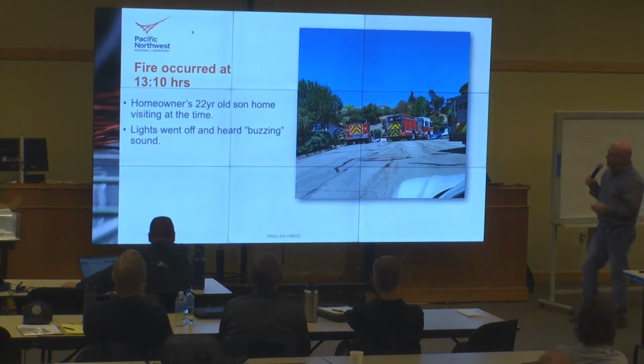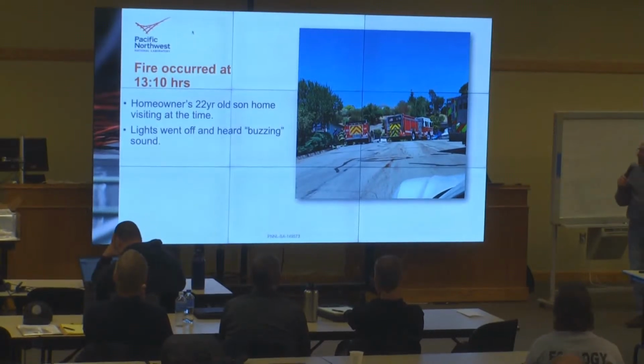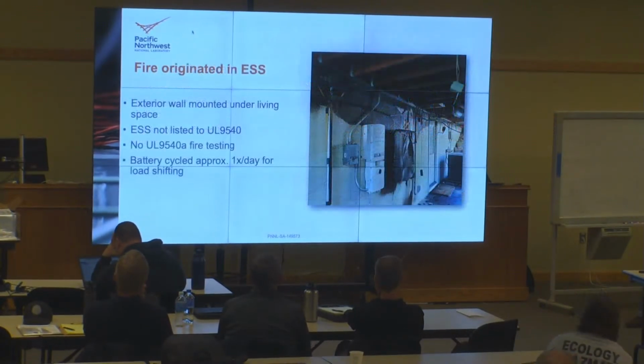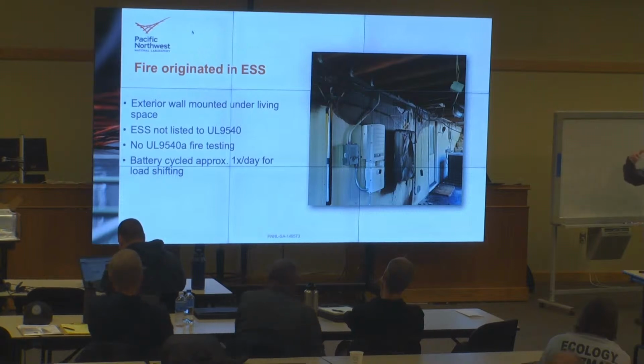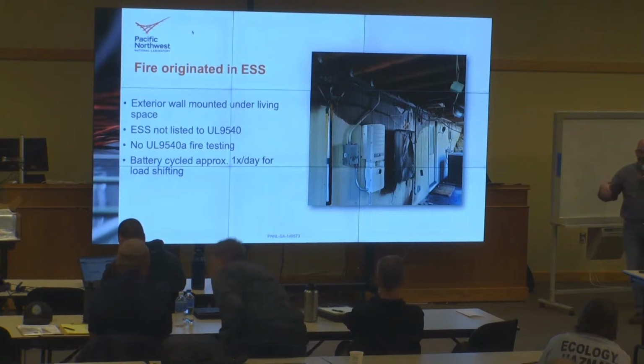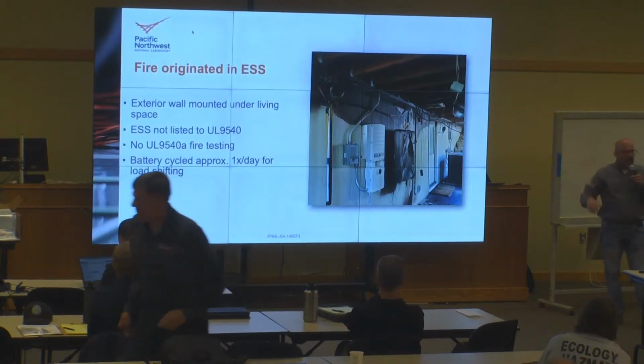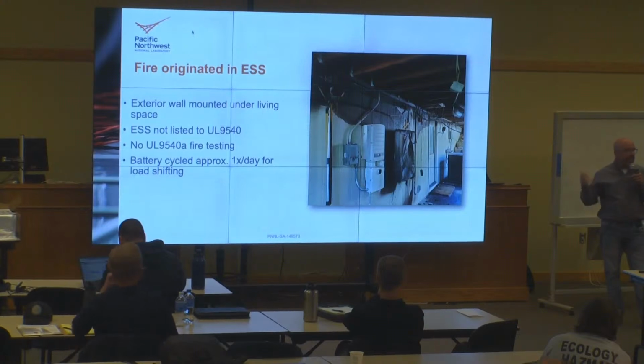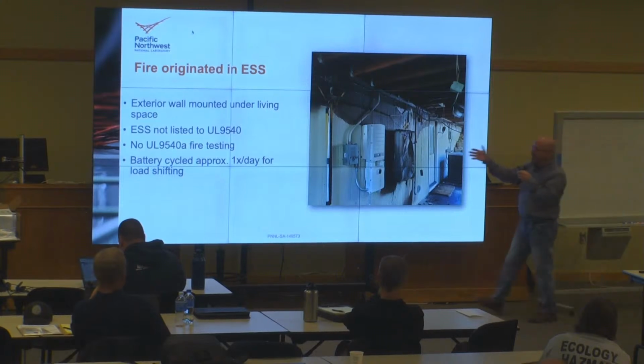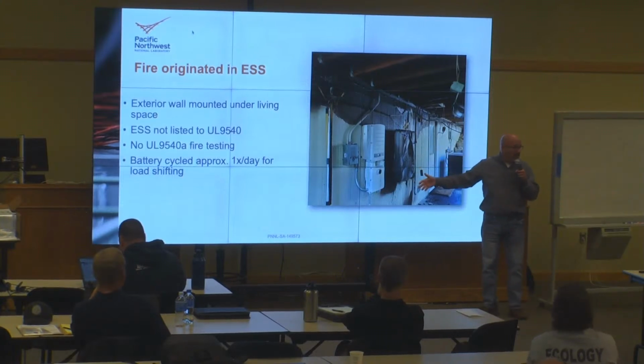Engine 19, my old crew. The homeowner noticed some buzzing about 1:10 in the afternoon, and the lights went off. Went outside, and this thing was on fire, rolling under the roof of the upper deck there. So the battery was used for what's called load shifting. It was running during the expensive times of electricity. I don't know if you guys have that out here, but in California, energy is more expensive from like 10 a.m. to 7 p.m. So they'll pull everything off of the battery during that time and then charge it at night. So once a day it was cycled. But at the time, there was no requirement for this to be listed to 9540, nor for fire testing.